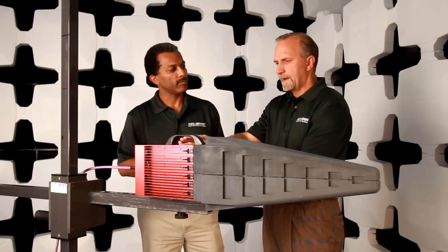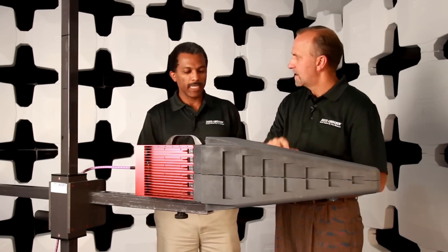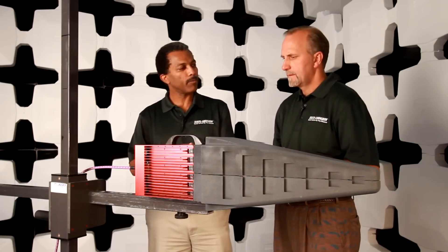So you have more than one amplifier and you have more than one antenna? Yes, in this module we've got three separate amplifiers. Each amplifier has two power sensors and power meters which measure forward and reflected power. And then each module is connected to a single log periodic antenna that form a three antenna array.